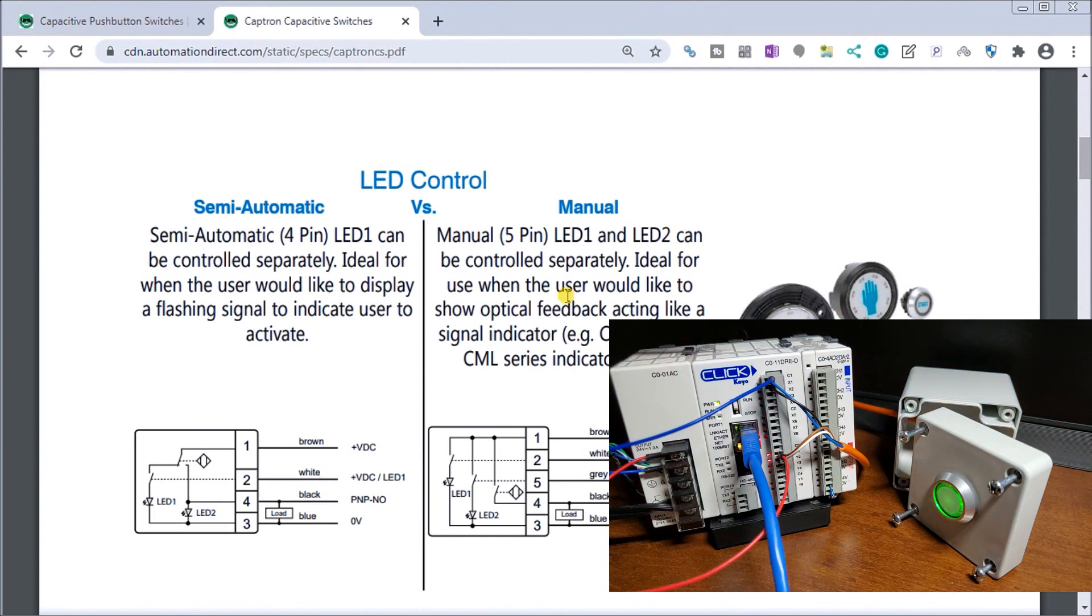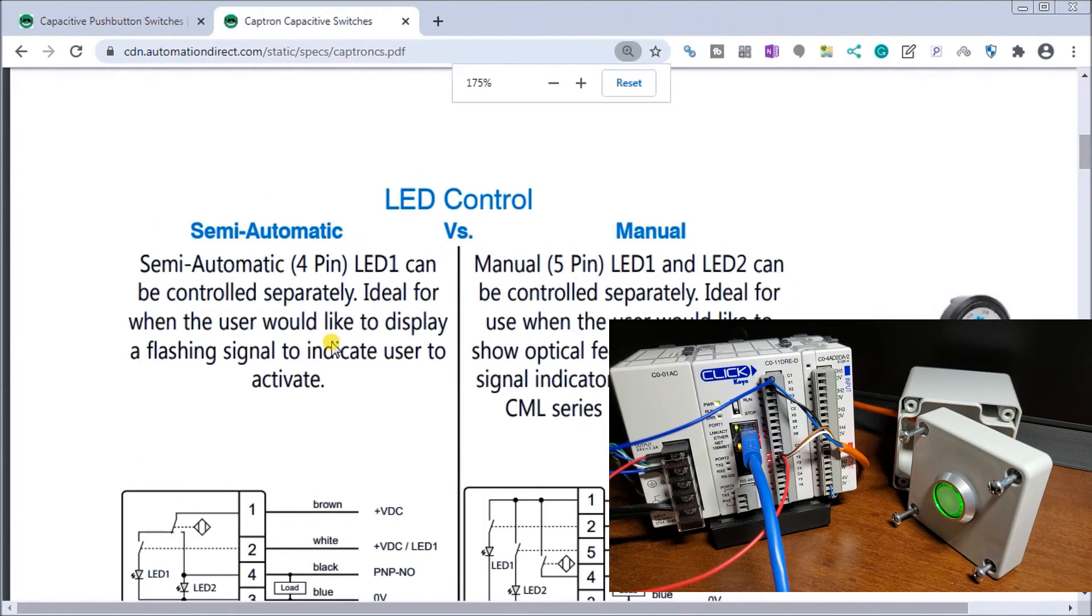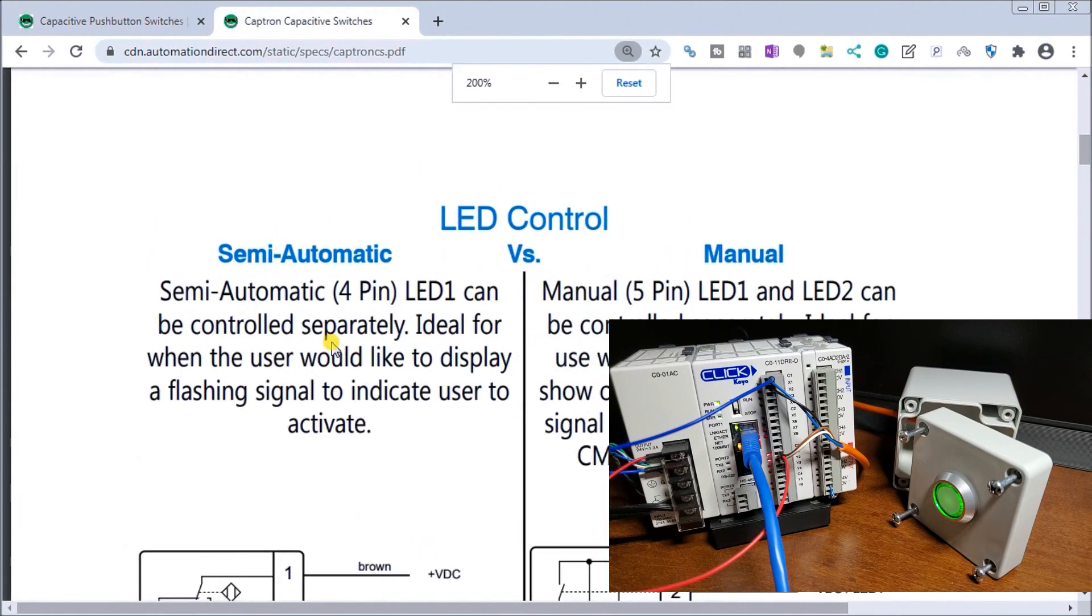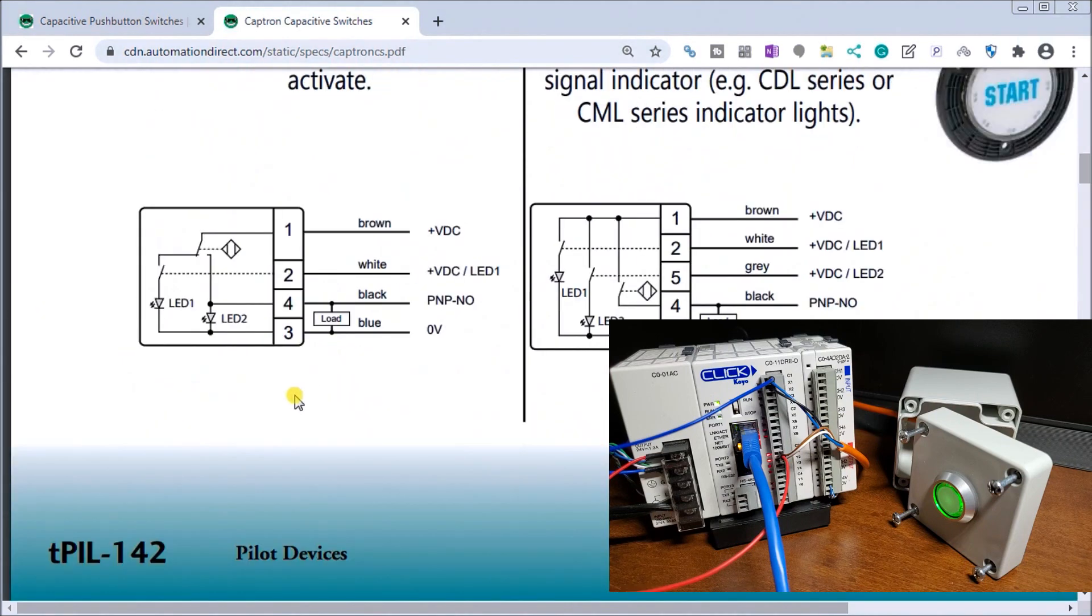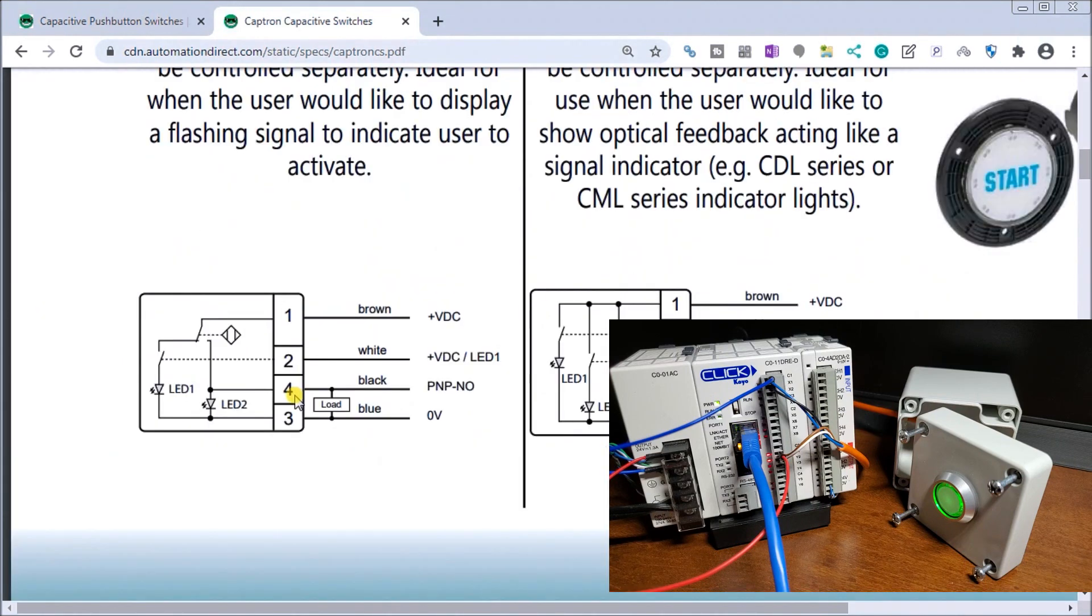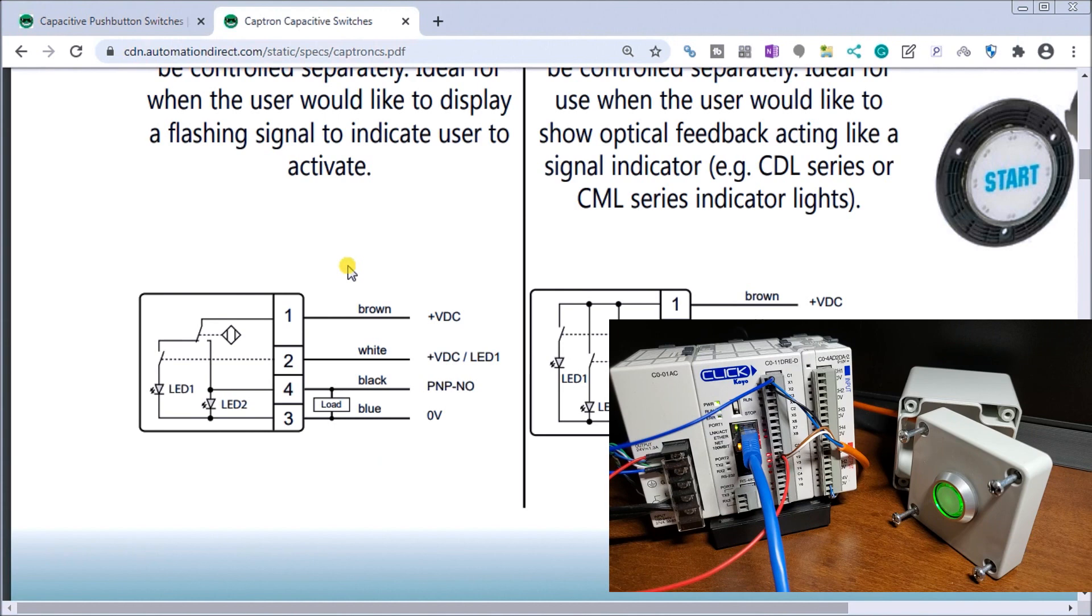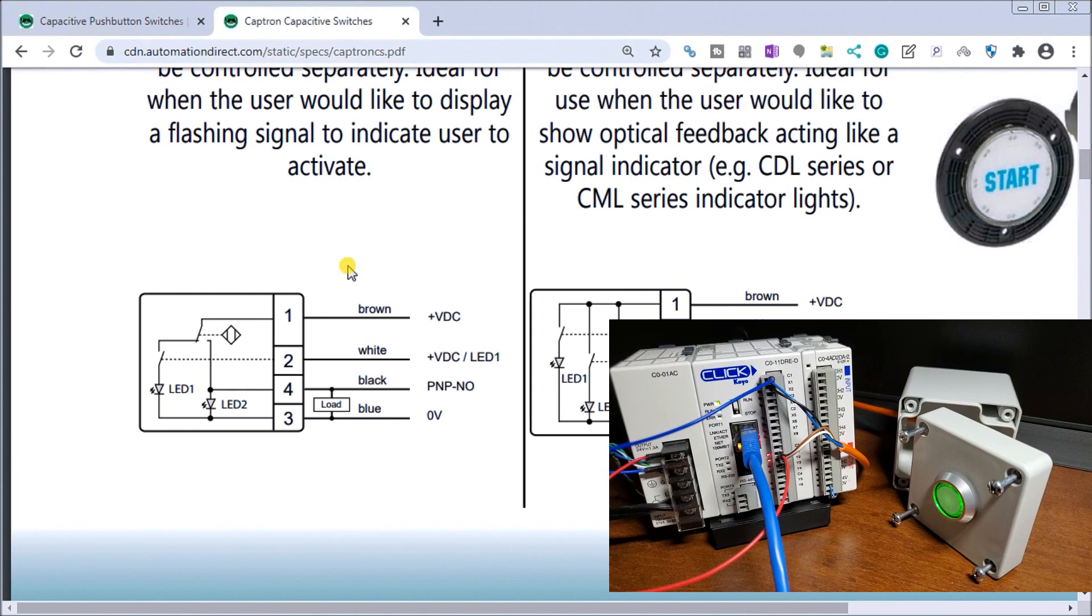And we have our wiring diagram here, so let's on our screen here let's just blow that up a little bit more. And this particular model is the static output, so as I touch it it'll turn on and off directly. It is a semi-automatic, so the red LED light will come on only when the sensor is being activated. And so we have an output that controls our green LED light which is actually coming from our PLC.